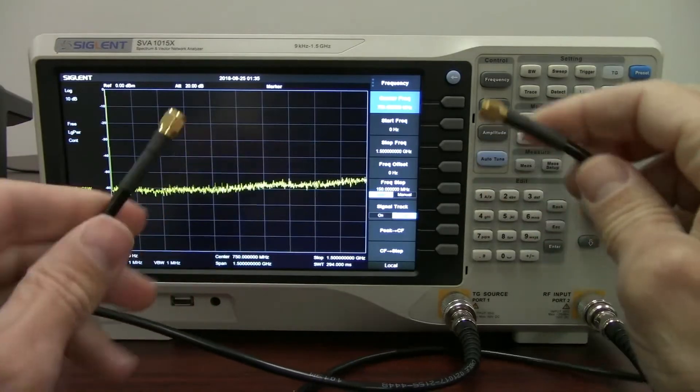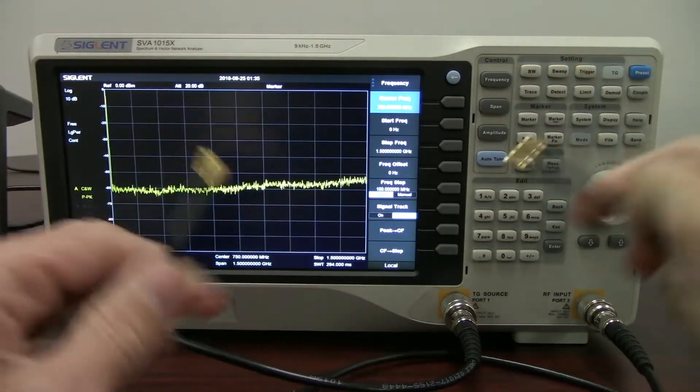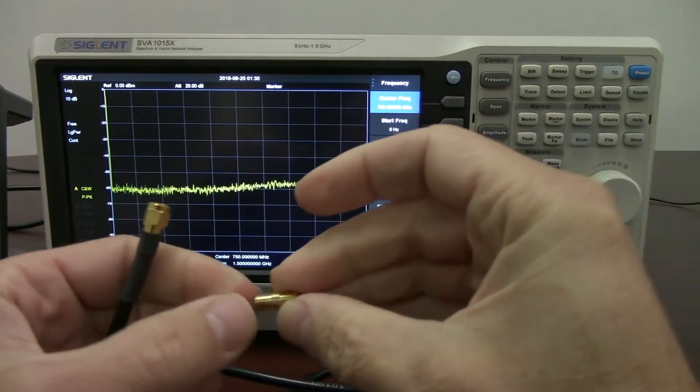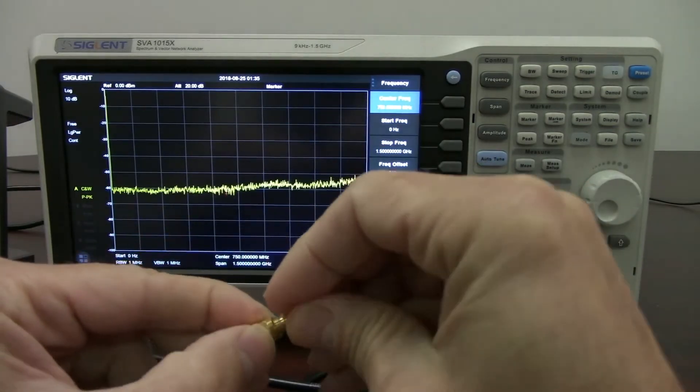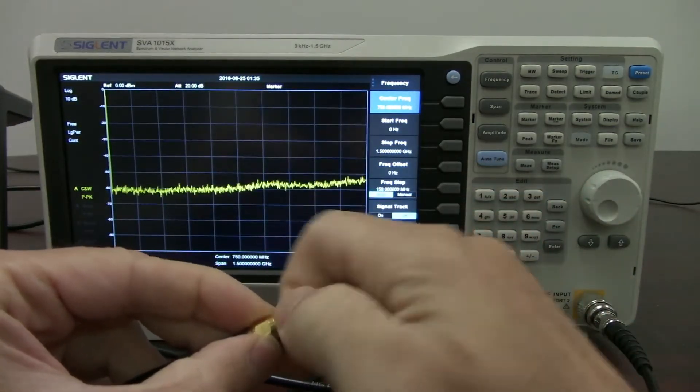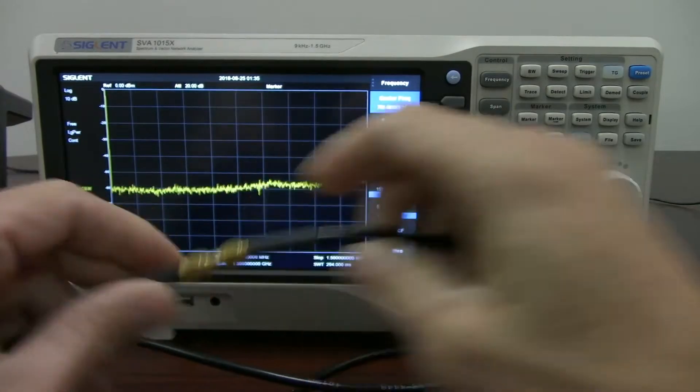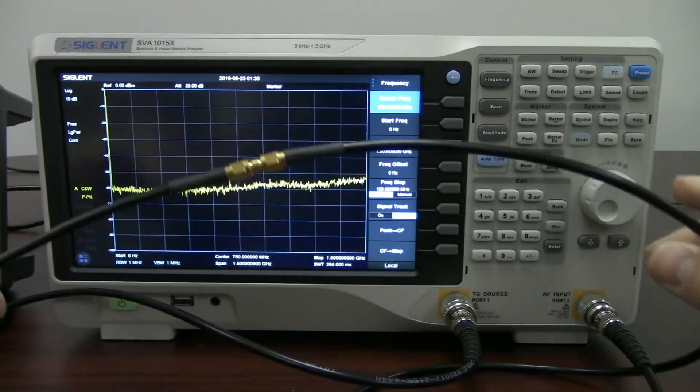But the first thing that we want to do for accuracy is we've got the two cables. What we're going to use is a through adapter. This is an SMA to SMA through adapter, and it just simply is going to couple the tracking generator output to the RF input. And so I'm just connecting these two up, nice and tight, and there we are.